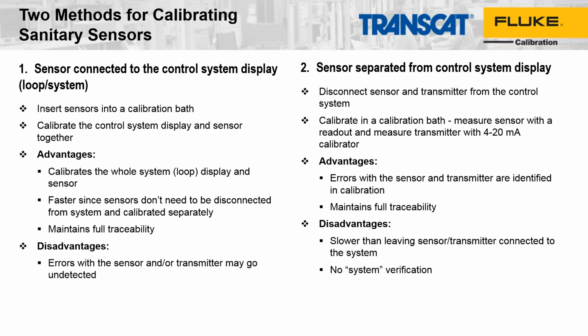The advantage of this type of calibration is that you are doing a loop calibration or a system calibration where the transmitter and probe get calibrated together. It's a kind of one-step calibration process. This is a little bit faster because you don't have to worry about disconnecting the sensor from the transmitter, and it does maintain full traceability. The transmitter and probe are calibrated as a system, so the traceability is fully intact. The only disadvantage is that sometimes there might be an issue with the transmitter or the sensor that might not be detected calibrating it as a system. And so the other method we have here helps take care of that by disconnecting the sensor from the transmitter.